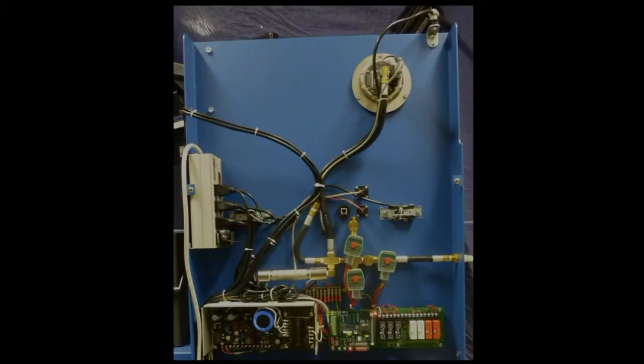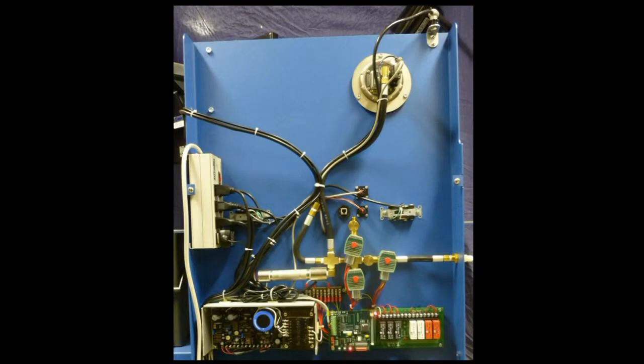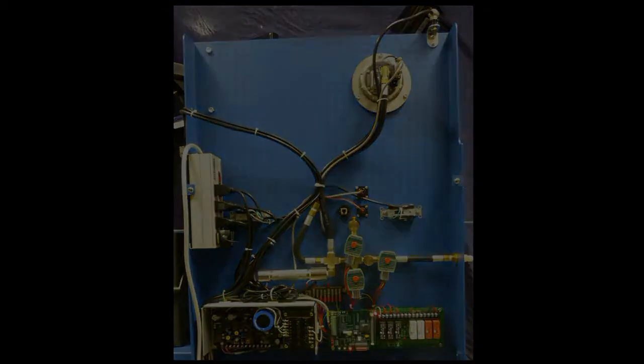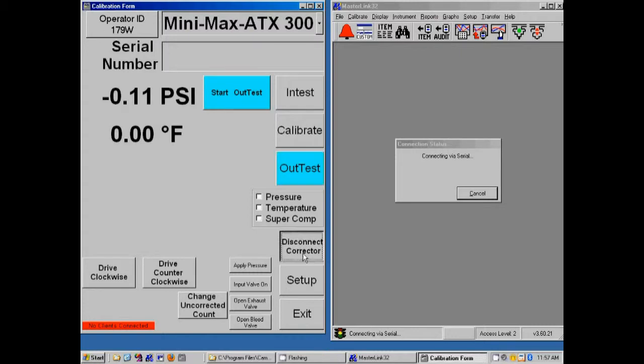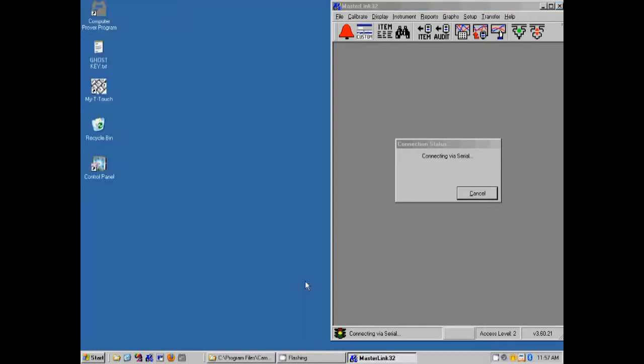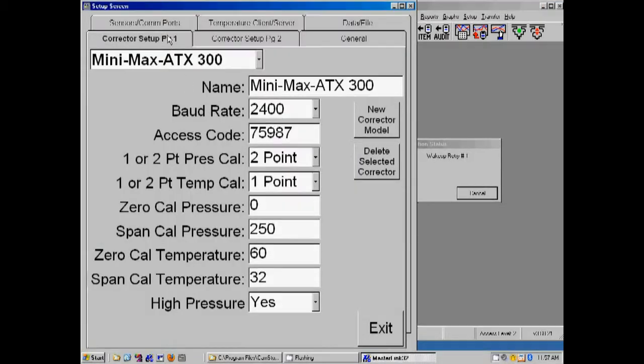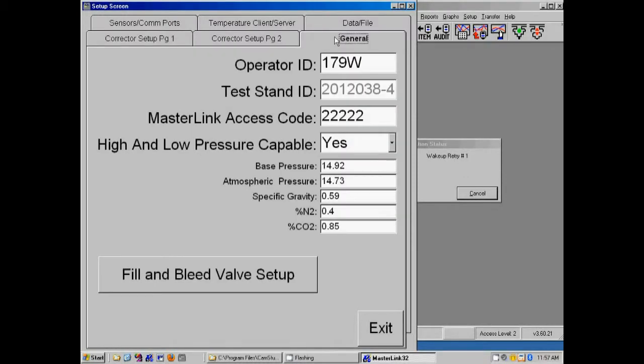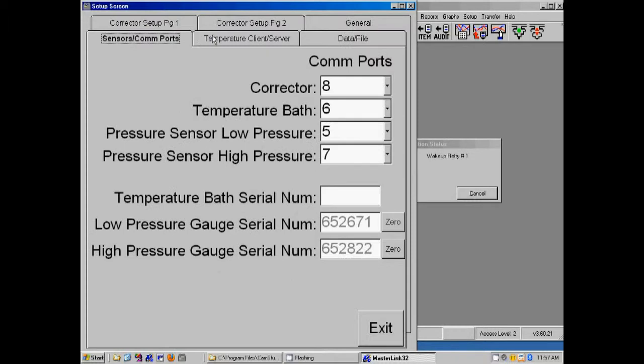With computer-controlled pressurization, the user-programmable test points are reached quickly without any user interaction. Measurement System software allows the operator to customize the parameters of a test. The operator can add or remove a corrector model by entering the setup menu. The type of test, number of calibration points for both temperature and pressure, and the pressures and temperatures to be tested are all user-programmable parameters.